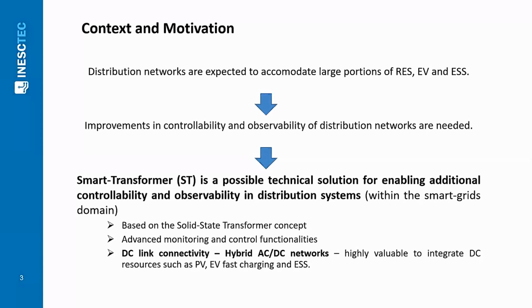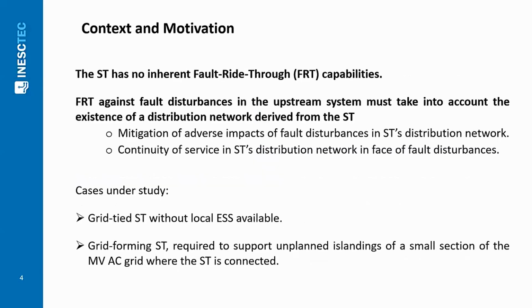It is based on the solid-state transformer concept, which opens the door for advanced monitoring and control functionalities. Besides that, it provides DC-link connectivity, which enables the formation of hybrid AC-DC networks, highly suited to connect DC resources. However, in comparison with the traditional low-frequency magnetic transformer, the smart transformer has no inherent fault ride-through capabilities.